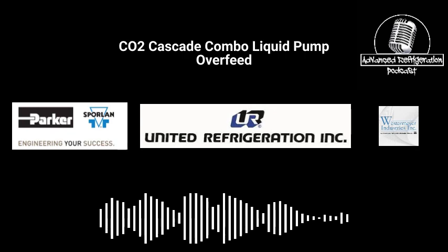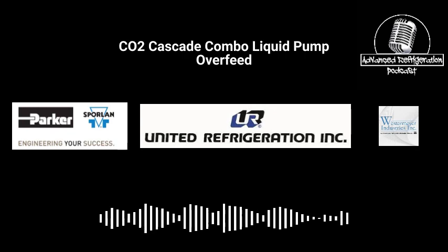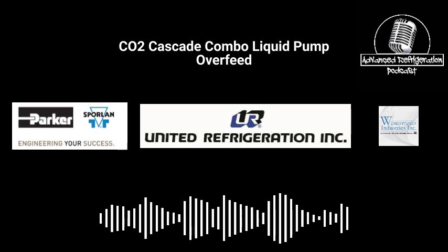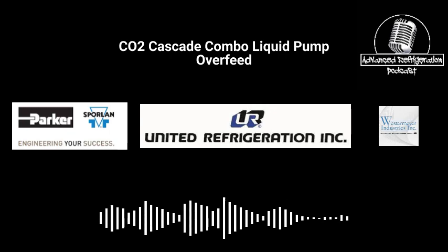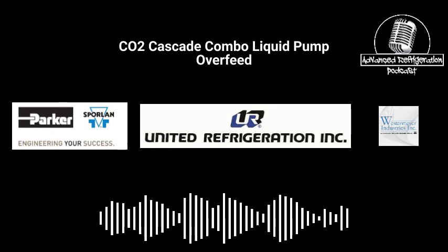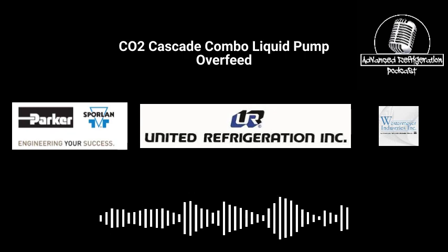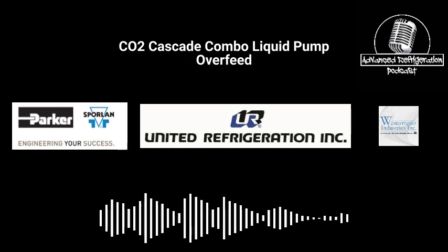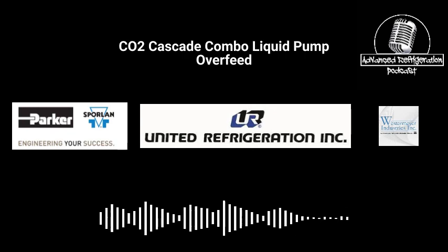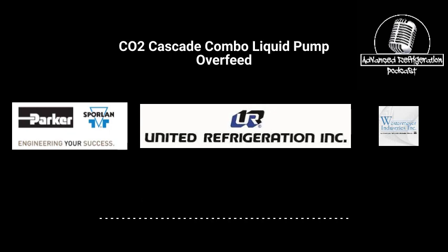So essentially what they do is they use that same liquid pump supply to feed other low temp cases. But in this instance, they actually have expansion valves. They're actually, or at least they're controlling the superheat on these, which then goes through the heat exchanger, back up through the suction of the low temp compressors, and discharges back into the heat exchangers, and the cycle just repeats.